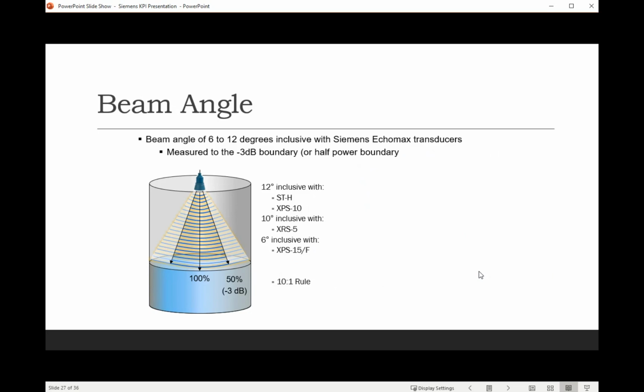Here's the nugget. There's something that we use called the 10-to-1 rule, which is kind of a rule of thumb that I use just for back of an envelope calculation if the system will work, which is for every 10 feet down that you're coming from the transmitter, I'm looking for a transmission source that's about 1 foot off of a sidewall. So if I'm looking down a wet well, and that wet well is about 25 feet deep, I'm looking to place that transducer about 2.5 feet, or 1/10 of the distance that I'm trying to measure. And generally speaking, in that case, if I have about a 2.5-foot radius or about a 5-foot diameter circle without a lot of obstructions in it, that's really going to be a good solid installation where we're going to have good performance.